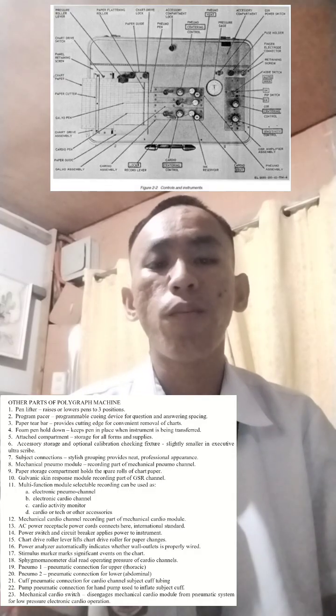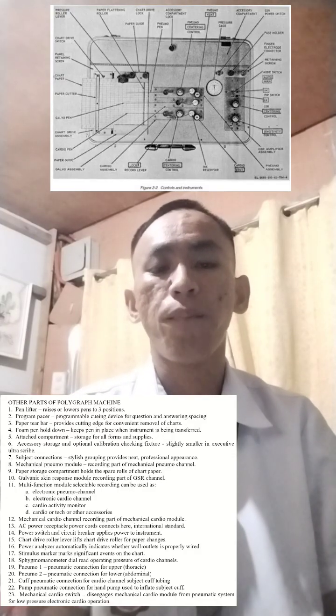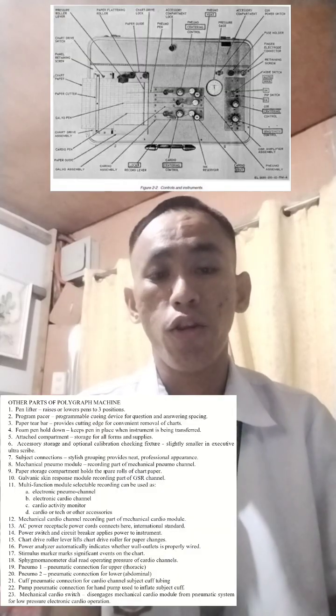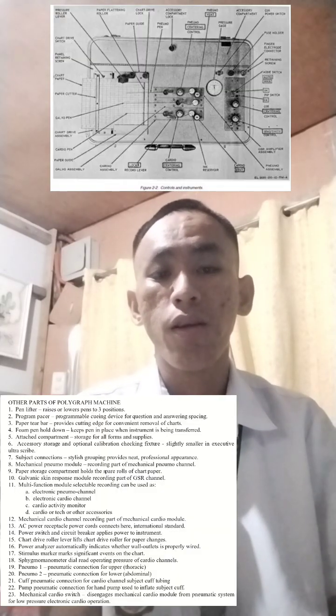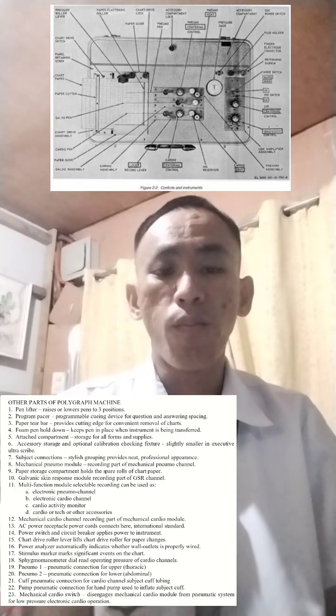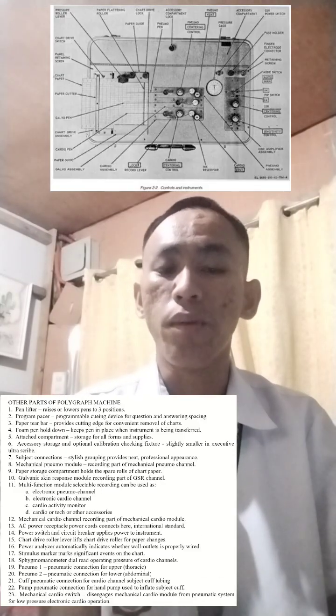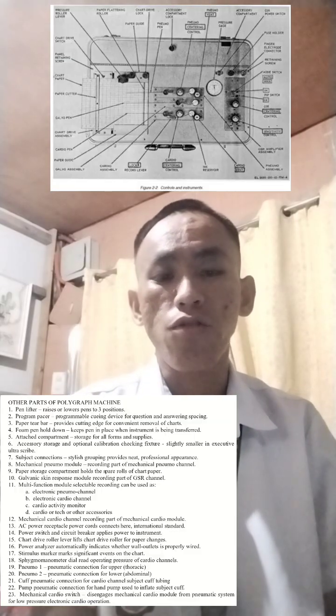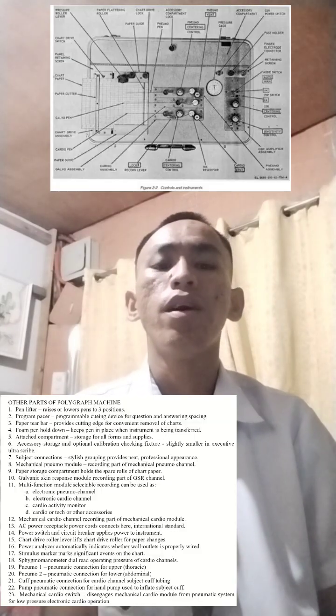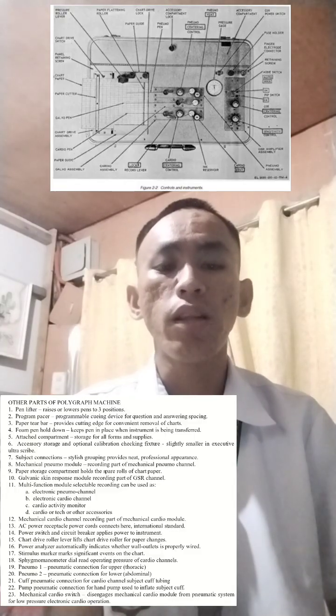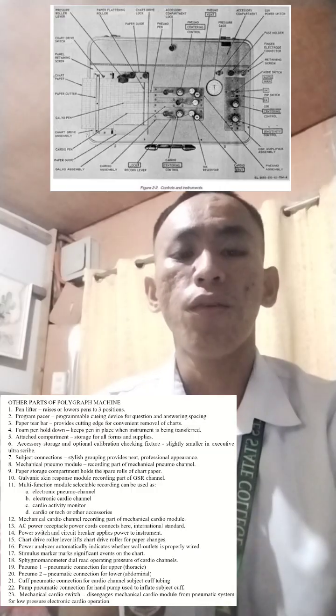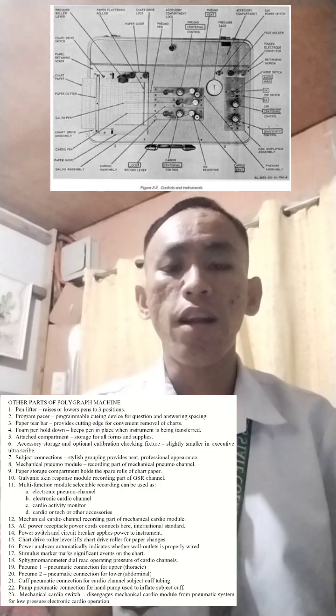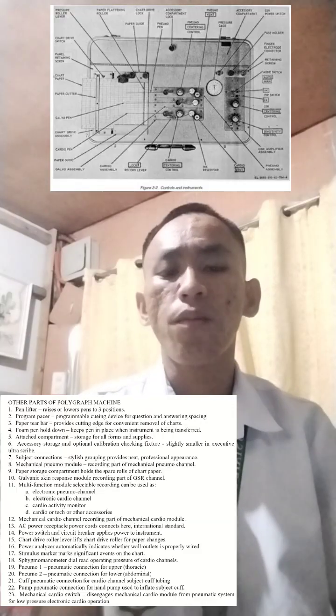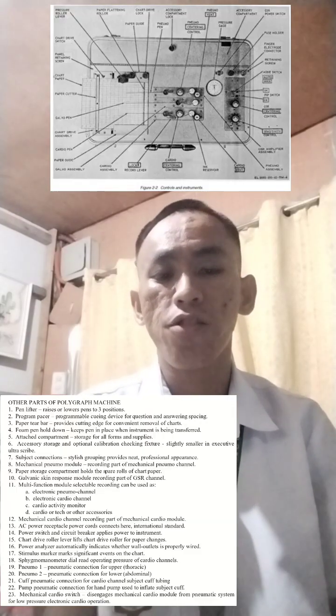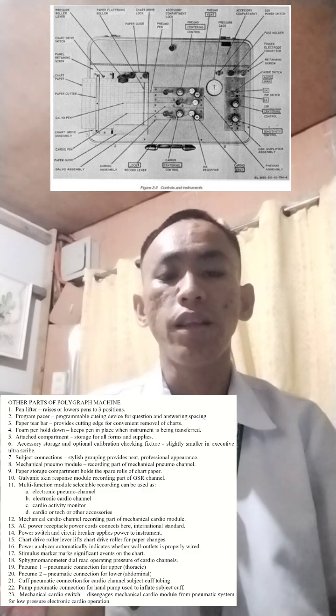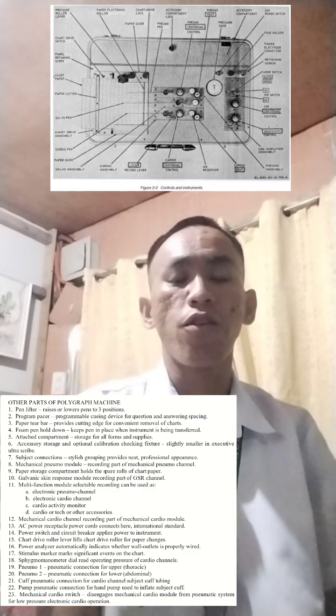Sphygmomanometer dial reads the operating pressure of the cardio channels. Pneumo 1, pneumatic connection for the upper. Pneumo 2, pneumatic connection for the lower abdominal. Cuff, pneumatic connection for the cardio channel subject cuff tubing. Pump, pneumatic connection for the hand pump used to inflate the subject cuff. And the last one, the mechanical cardio switch. It disengages the mechanical cardio module from the pneumatic system for low pressure electronic cardio operations.